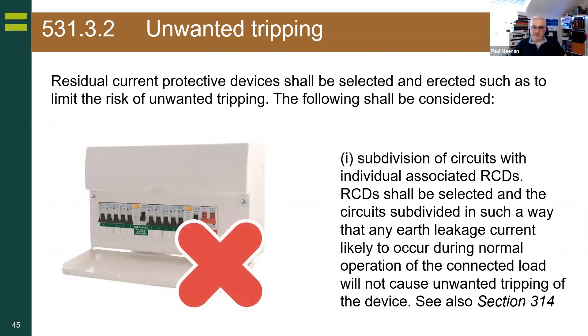However, there is a push or a recommendation, which I wholeheartedly agree with. So some people argue that that's the death of it. I think we'll still see it around for a few years yet, but I do think we are moving away from the split load board. There's your RCBO board. What it also says is residual current devices shall be selected and erected to limit the risk. The use of RCBOs for individual final circuits.